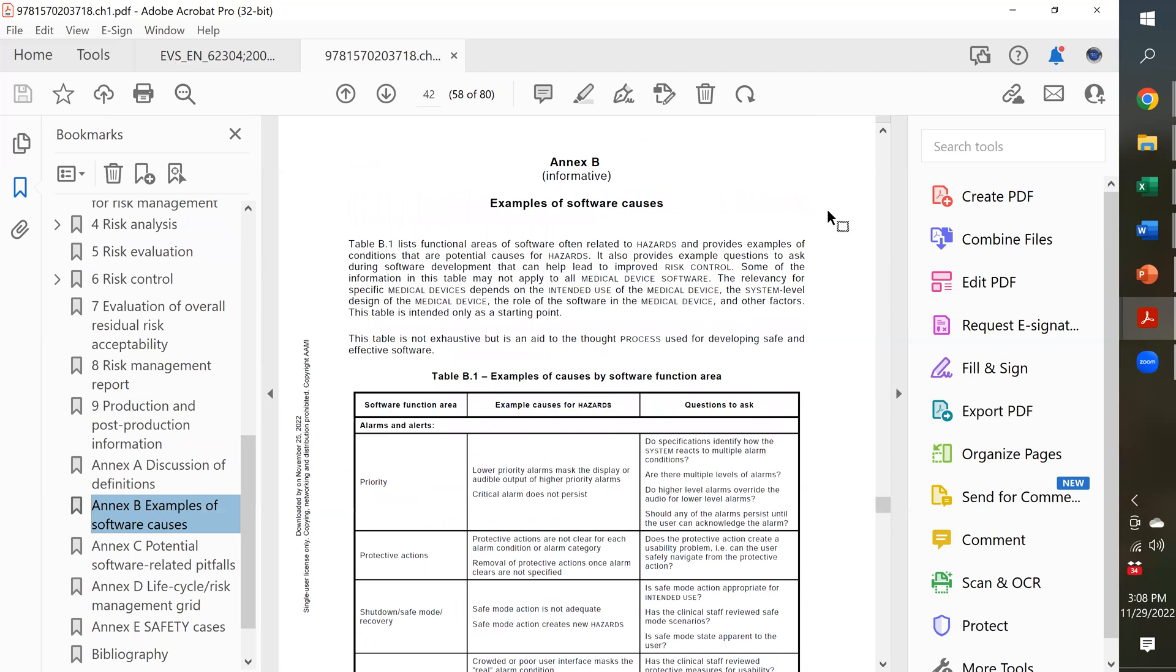In Annex B, they give examples of things that can go wrong in software, and they give you examples of hazards that you should be putting in your hazard analysis. And they also give you examples at the very end, in the last table in Annex B, of how you would verify that your risk controls are adequate for your software hazards.